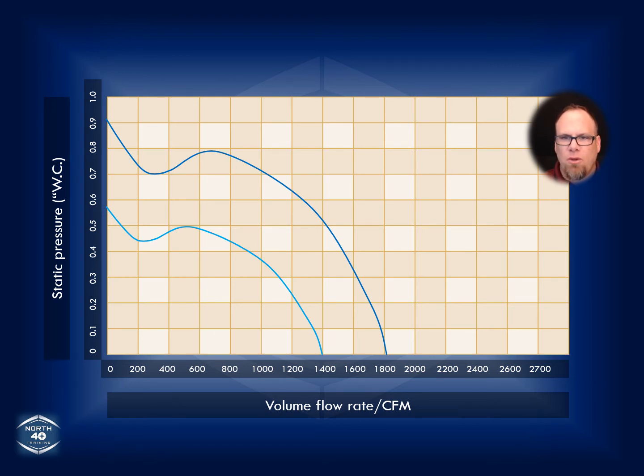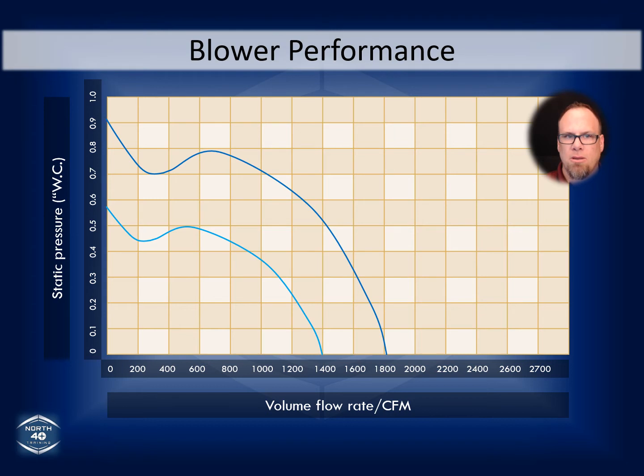Well, if you were to use your manometer and stick it in those areas of the furnace that you made the penetrations in before and after the blower, like we just talked about, you'll find a resistance reading. And on that resistance reading, you then take that back to the chart, and that chart is going to tell you what the CFM value is for that resistance. Okay, and before we move off of this chart, we're gonna talk about this a little bit more, but before we move off this chart, there's something that we really need to address, and that is filters.